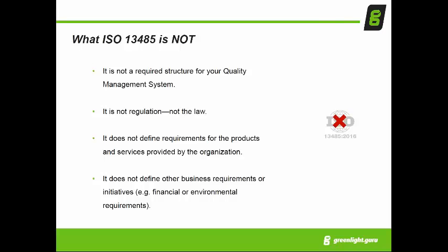I'm only confused because of the way you used this slide and said not required, not law, not required, and then you said required. Well, okay, so ISO certification is a voluntary thing. If you're ISO certified, it is telling the regulatory world that you have implemented a quality management system that has been objectively evaluated and audited by a recognized third party, a registrar.